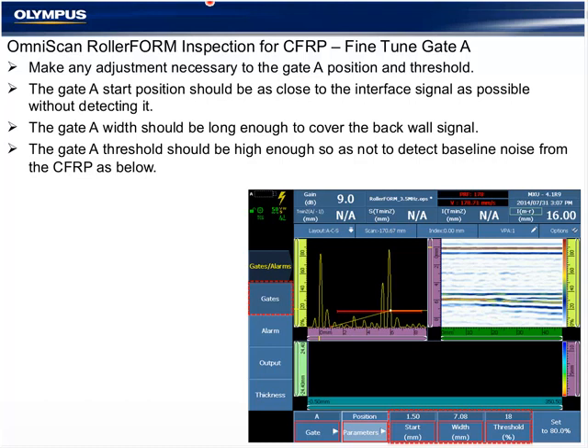Another question: is there an encoder-less version for a purely manual inspection? There is not. I assume that would just be for a cheaper or less expensive version of the RollerFORM. But the RollerFORM and the OmniScan are capable of using time mode for a time-based C-scan. You could just scan completely in one direction nonstop, but there wouldn't be any relationship to the scan axes.